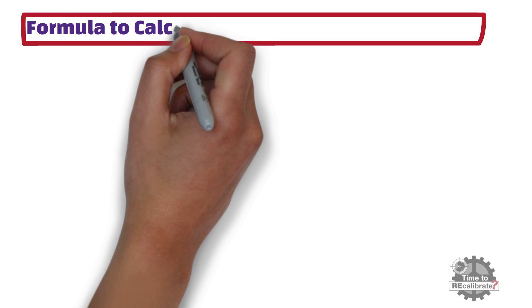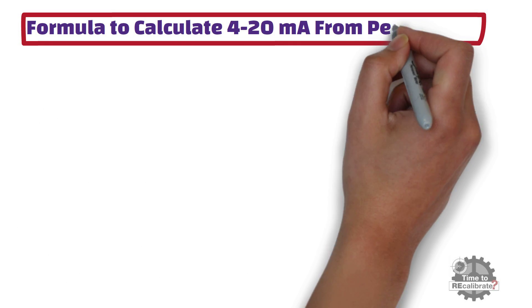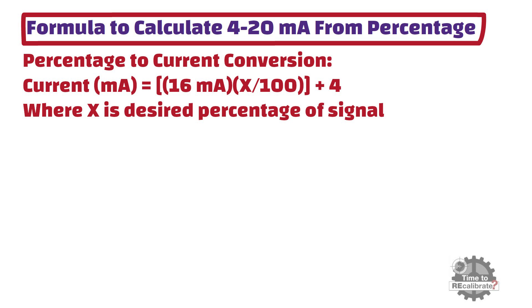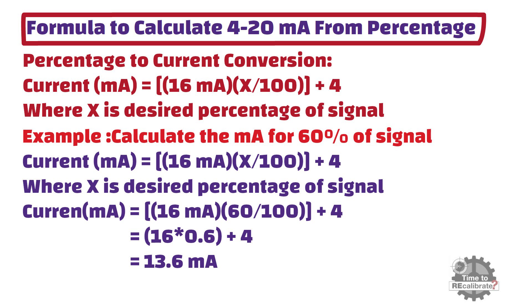In this section, we will learn about the standard formula to calculate 4 to 20 milliampere from percentage. As you can see, this is a standard formula to convert any percentage process value into a milliampere value. Let's understand this formula by taking one example: calculate the milliampere for 60% of signal. Put 60% in place of x in this equation and do the simple math calculation. You will get 13.6 milliampere.